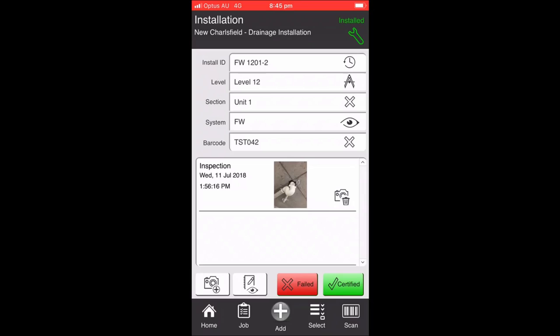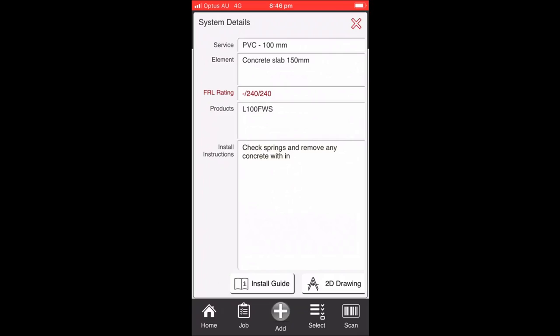Navigating to FW1201-2 will take us to the installation screen. On the installation screen, you get a lot more information about that install, including drawing information and information on the system that's been installed. If I click on the eye icon, we can actually have a look at the system. In this case, this is a PVC pipe of 100 mil going through a concrete slab using an L100FWS product. There's some instructions there on the installation for the user - they need to check the springs and remove any concrete. There's also links to be able to view the installation guide and the 2D Drawing.